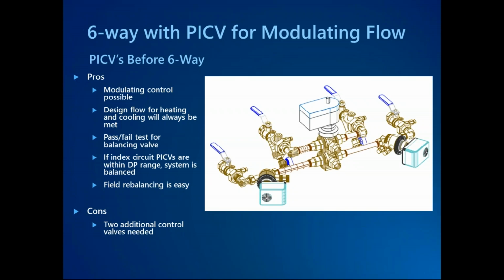By using PICVs, we're getting that modulating flow control. We're getting the design GPM. It's going to react to differential pressures, and rebalancing in the field is relatively easy, as all PICVs have some way to adjust the max flow in the field. The issue with having the 2 PICVs on the branch side or the main side of the 6-way is that, again, you're providing 2 valves, so it's 2 additional actuators, and you're adding more complication to the building management control.